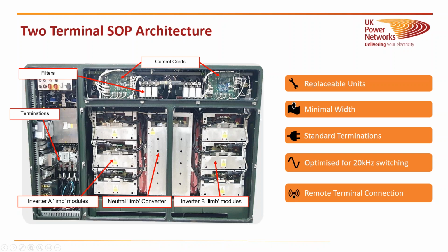And you can't quite see it, but at the back there, the red, where it's actually copper, there's a DC bus bar. This has been built with replaceable units in mind, so you can quickly swap in and out various parts of this. You've got the inverter limb modules here that can be lifted out, and same with the neutral converter and the control cards as well. So it's been designed with quick maintenance in mind.